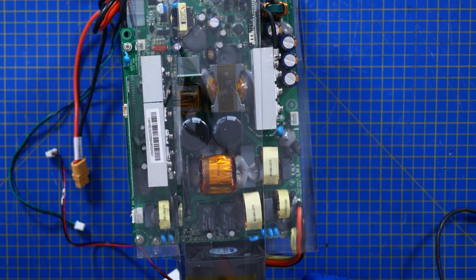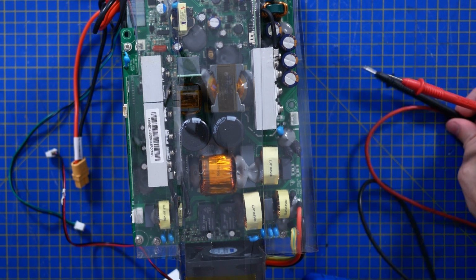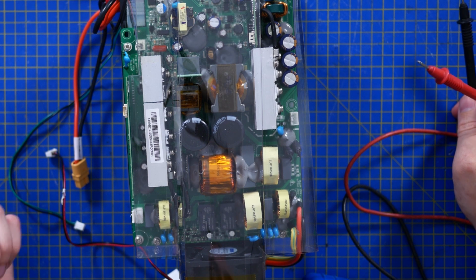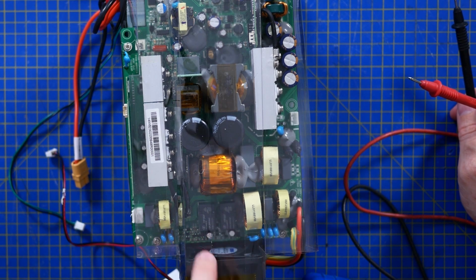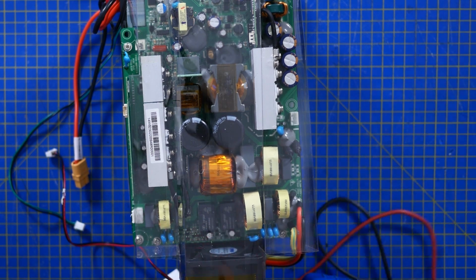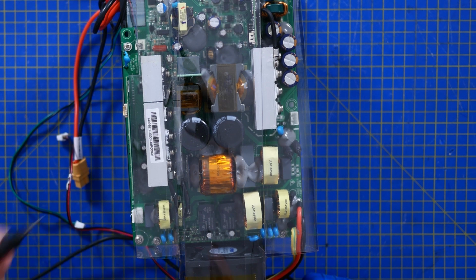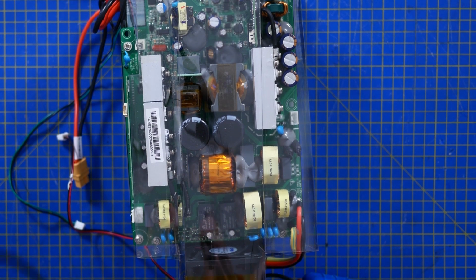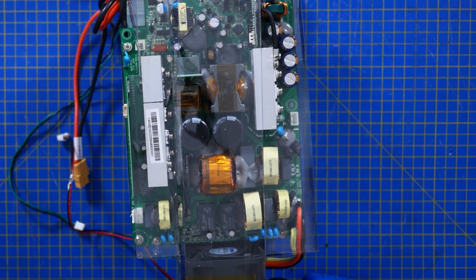The fact that there is a change over time could be the time it takes for the inverter to start, but it could also be the time it takes for a pair of relays to switch over from mains to battery. No, that's off. So I strongly suspect that pair of relays down there, rated at 10 amp each, are what switch this from battery to mains throughput. That's a really nice feature.